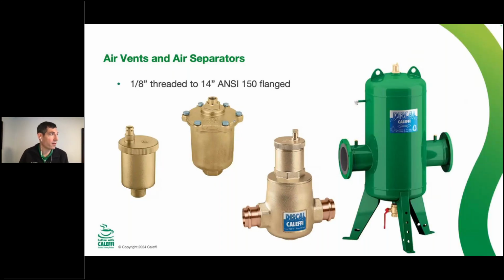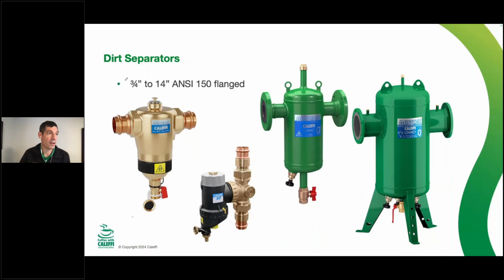So to wrap up here, air vents and air separators. Air vents for this side here have the same functionality, from 1/8 inch up to big air separators. And then from 3/4 to 14 inch, it's the same device, just a slow spot in the system with a coalescing mesh to help separate the air. Dirt separators, same thing, 3/4 inch to 14 inch. All these devices are going to look similar on the inside. This has a polymer media. This is stainless steel because we have to weld it together. Otherwise, you'd melt the polymer there.